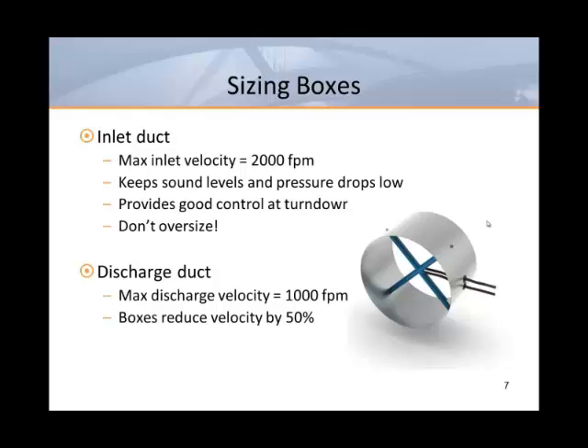As far as discharge ductwork, I like to think of boxes as devices that reduce velocity by 50%. If you have 2,000 feet per minute going in, you shouldn't have more than 1,000 feet per minute coming out. Discharge ductwork should therefore be sized for no more than 1,000 feet per minute. In cases where grills will be tapped directly into the sides of the discharge duct, I would design for no more than 800 feet per minute to prevent the possibility of room air being induced into the first few grills.